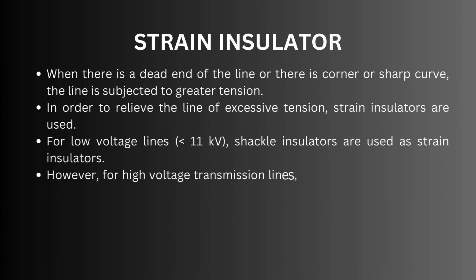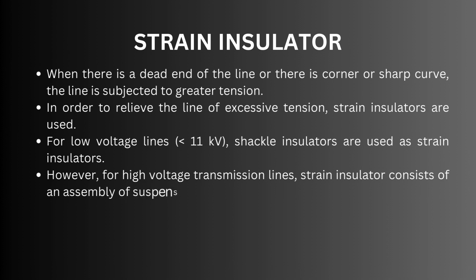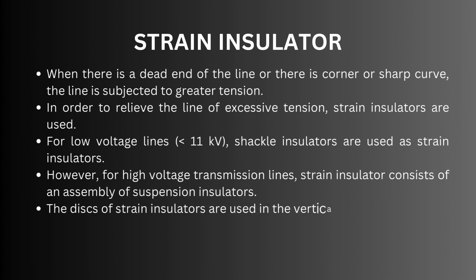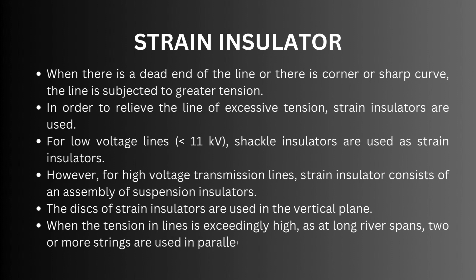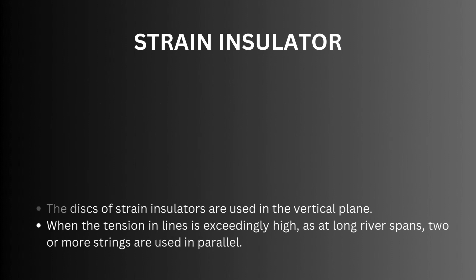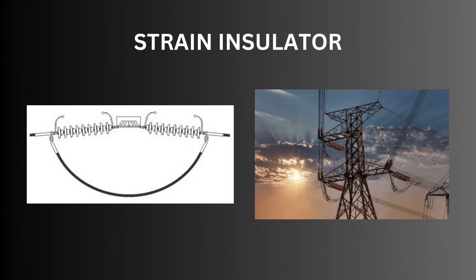However, for high voltage transmission lines, strain insulators consist of an assembly of suspension insulators. The discs of strain insulators are used in the vertical plane. When the tension in lines is exceedingly high, as at long river spans, two or more strings are used in parallel. The illustration depicts a strain type insulator.